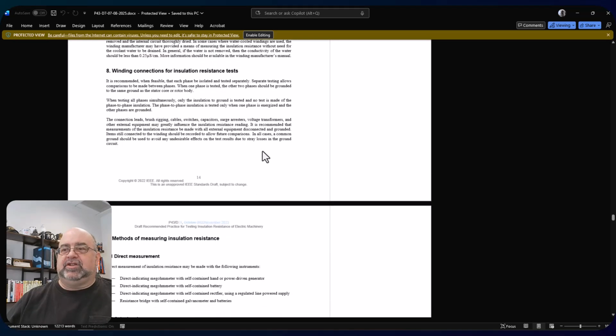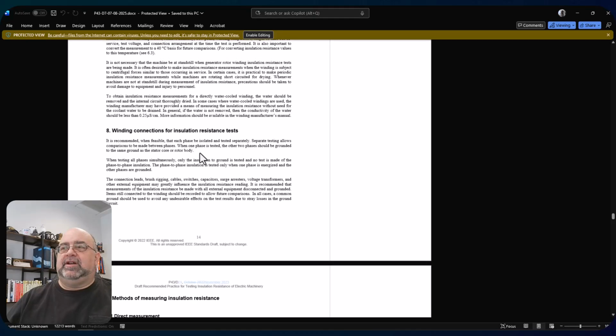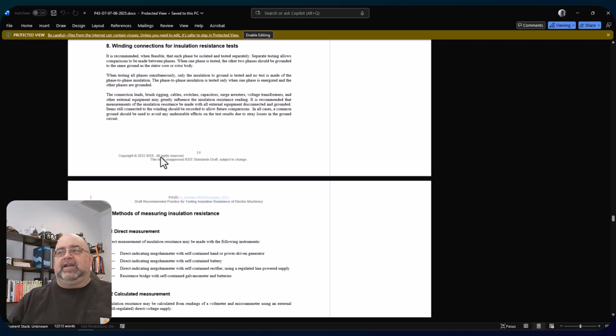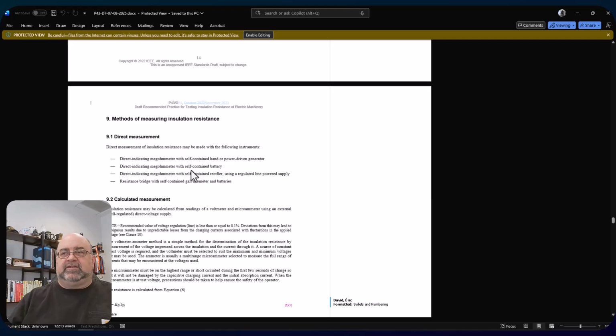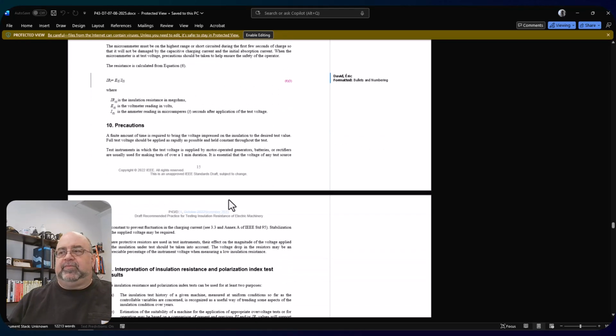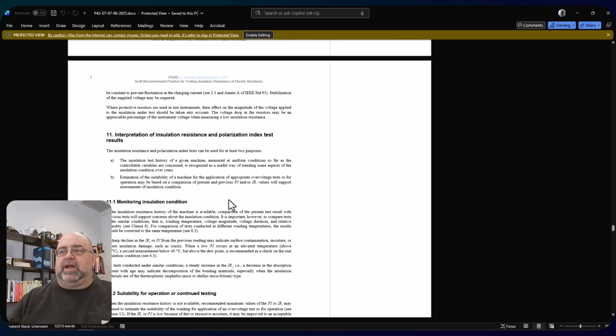Okay, winding connections. So here we go. Recommended when feasible that each phase be isolated and tested separately. Separate testing allows comparisons to be made. That would mean that in an AC motor you would break the Y connection. You're not going to find that in most small machines. So this is meant for larger machines again. Again, most of the people sitting on these committees are, oh, did I miss it?